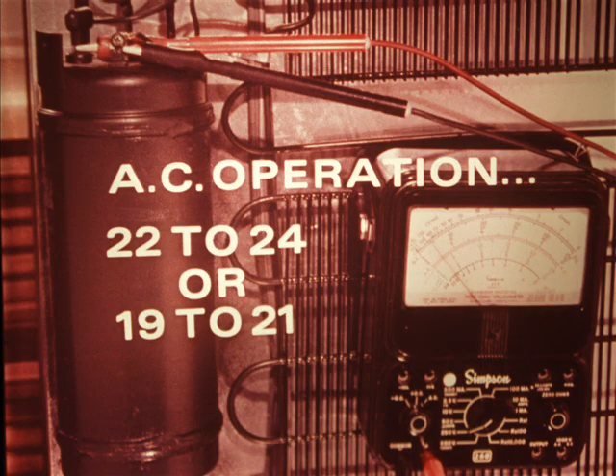Then, leaving the 12-volt source connected, plug in the refrigerator 120-volt power cord to a known good source. On 120-volt AC operation, the meter should read 22 to 24 volts for the 7.5 cubic foot model and 19 to 21 volts for the 6 cubic foot model. If the two readings are okay, the power supply and switching device are all right.